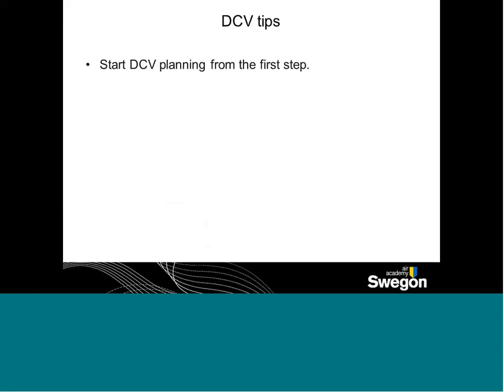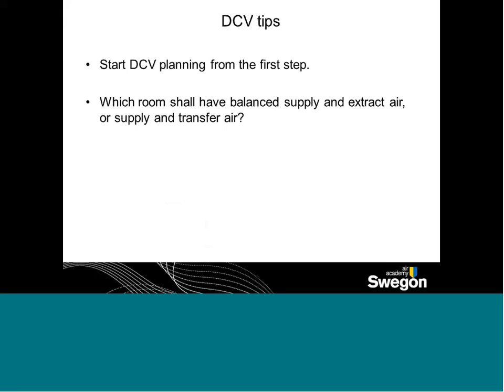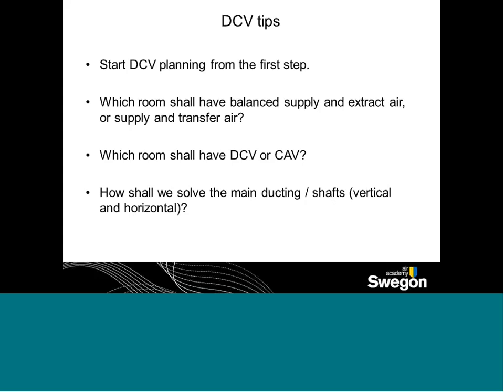Some tips on DCV systems: if possible, always start planning for DCV systems from the first step — don't try to take another system and convert it into one. You need to start with a clean sheet of paper. You need to understand which rooms need balanced supply and extract, and in which areas you need transfer grilles, perhaps into a corridor. Which rooms should have CAV as opposed to DCV, and how will that affect how the system remains in balance? And how are you going to size the main ducts and shafts, given the space available, including the effect on the central air handling system?